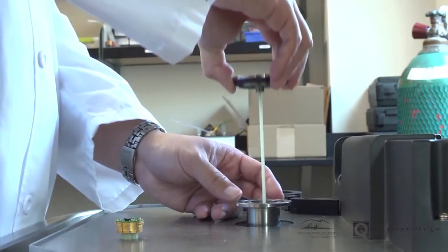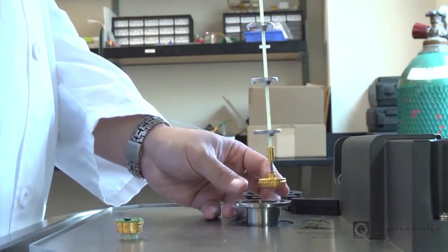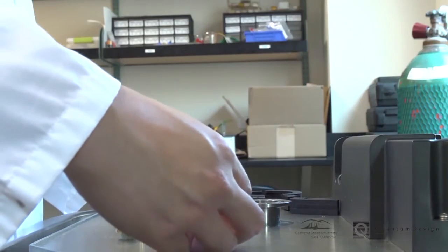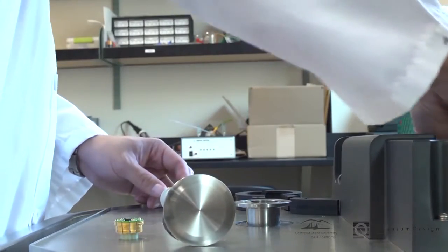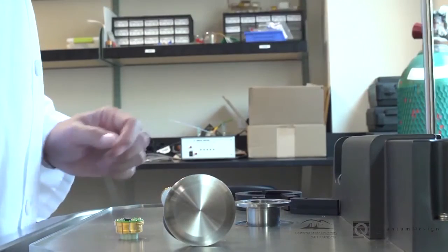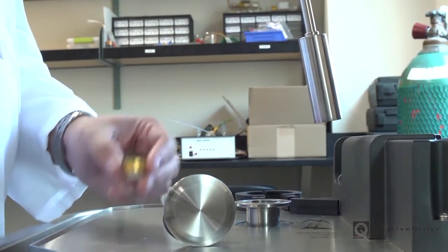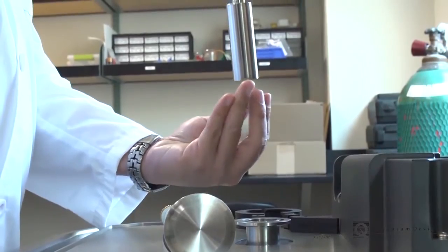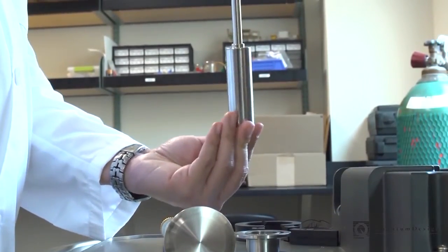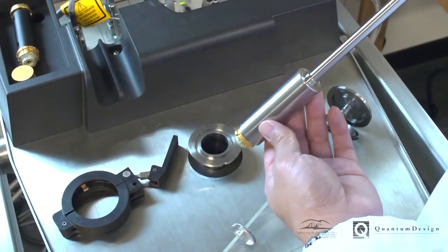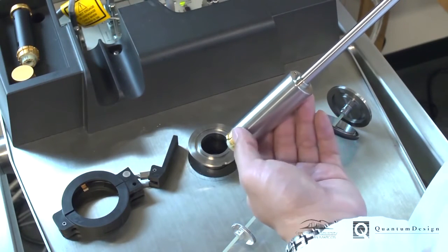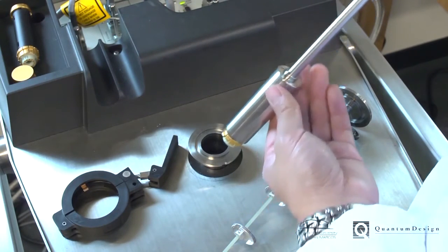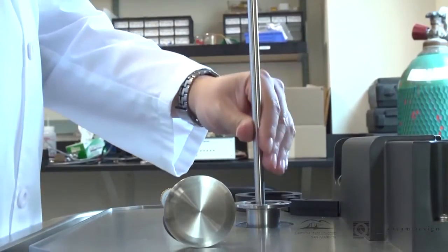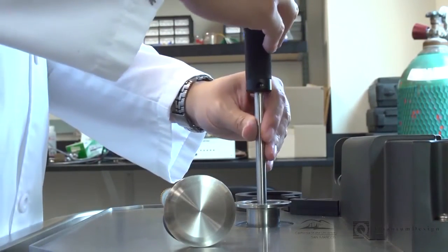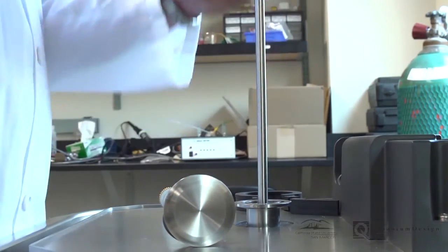Remove the baffle, and lock the puck into the puck insertion tool. Make sure it's snug. The notch is important, as the VersaLab is keyed such that the puck notch faces you. We recommend inserting the puck with the notch pointing 90 degrees away from you, and then rotate the tool. When you feel the puck slip into place, give it a nudge downwards and unlock the tool. Remove the insertion tool and close the baffle.